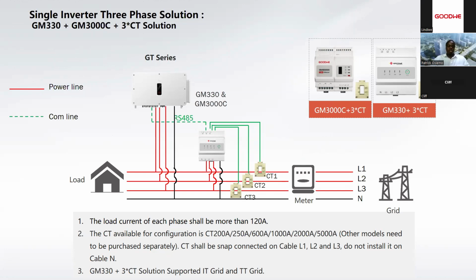So in this case, you'll be installing the GT series inverter along with the GM 330 smart meter or GM 3000C smart meters. This is for the three-phase solutions. The CTs connecting to the GM smart meters, GoodWe smart meters, are actually third-party CTs, with a secondary CT rating of 5 amps. The primary can be between 200 to 5,000 amps.